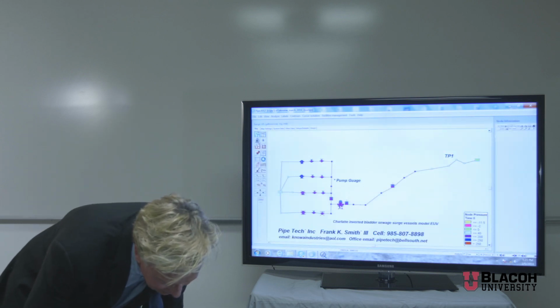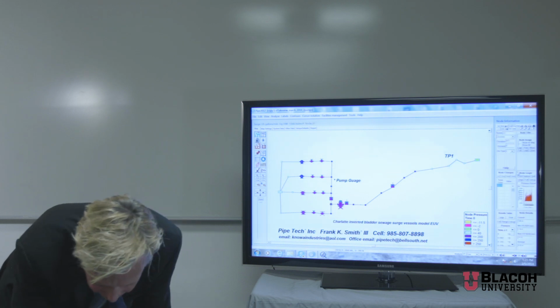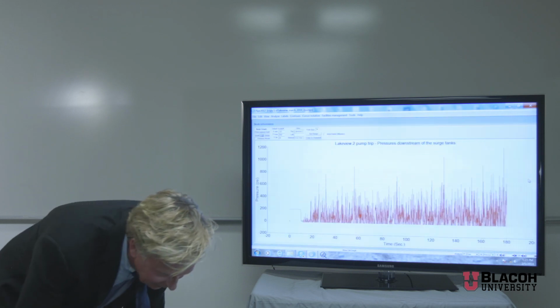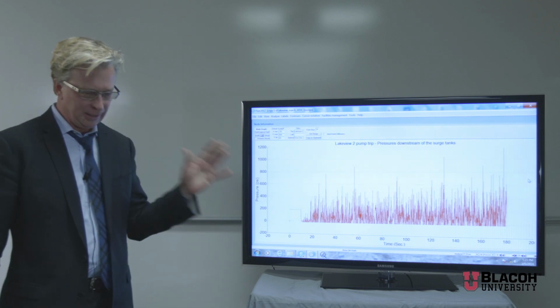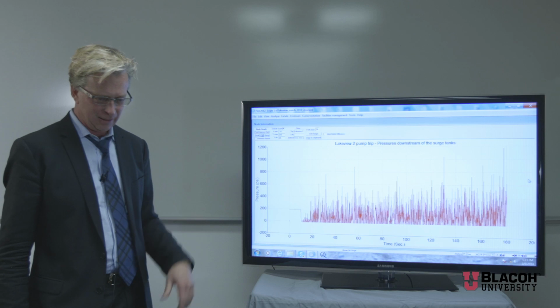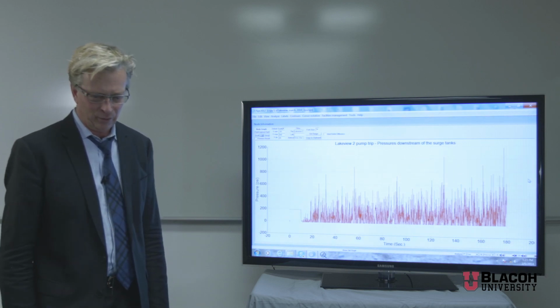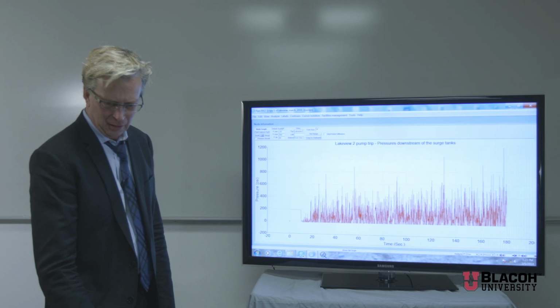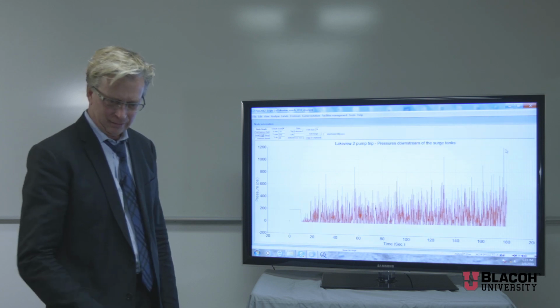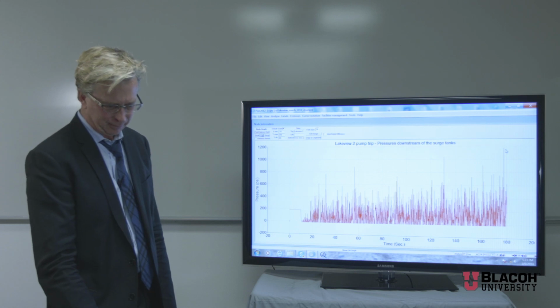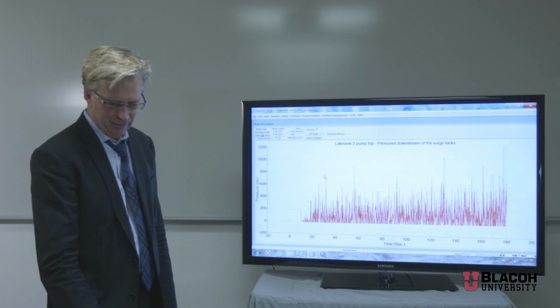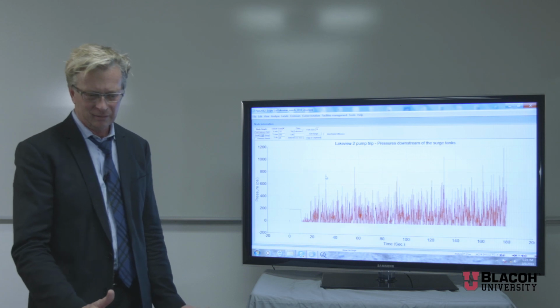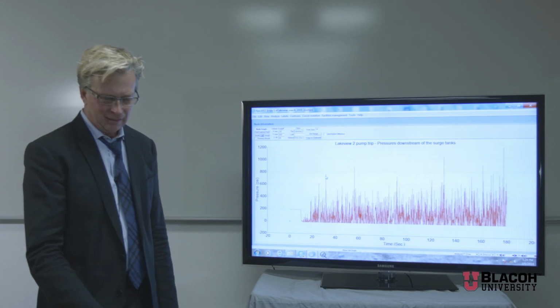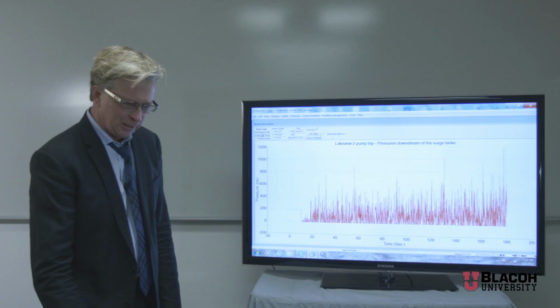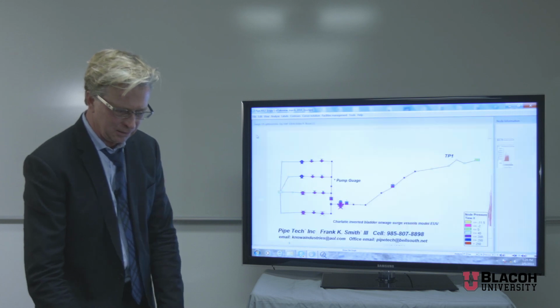So we'll grab a node in the pump station. And the bottom line is it goes from 180 psi to a vacuum condition. It's oscillating back and forth, and those crazy pressures were coming somewhere back in the end. Pressure, vacuum, pressure, vacuum. But the piping's good to 200, 300 psi max. We're at 800 psi there, so there's no telling when it blew apart. So that's our problem, and here was our solution.